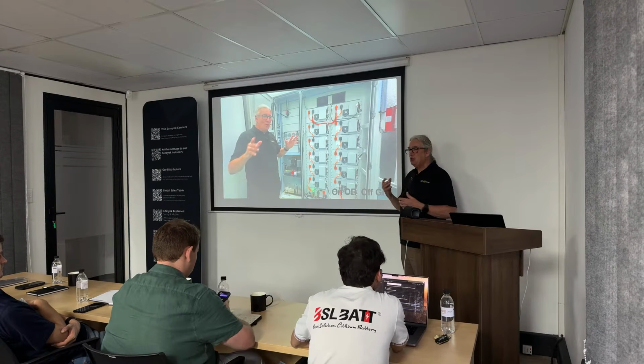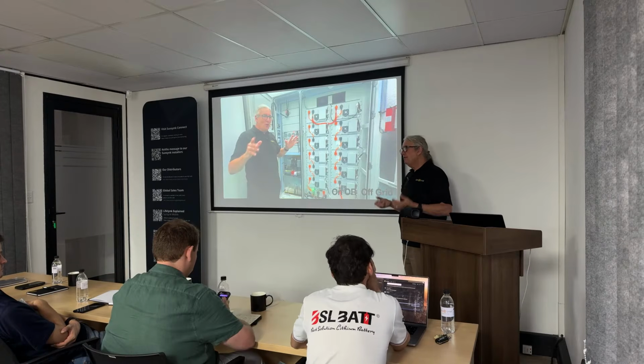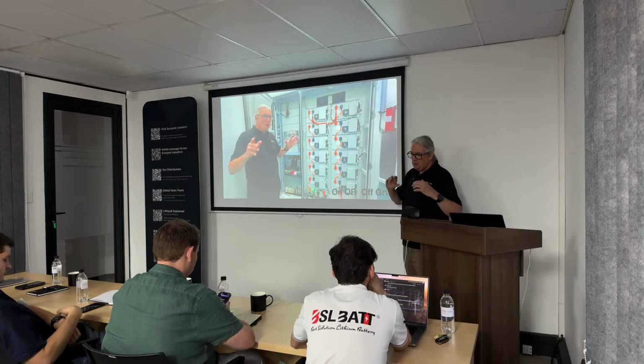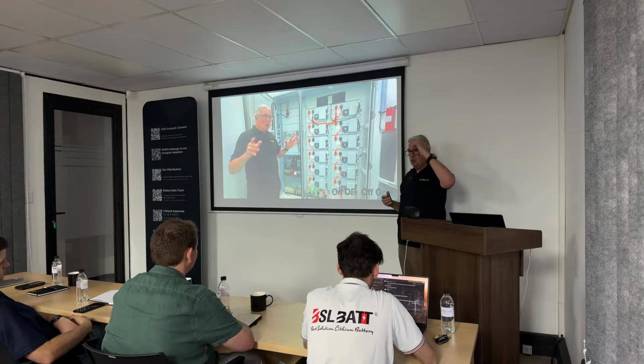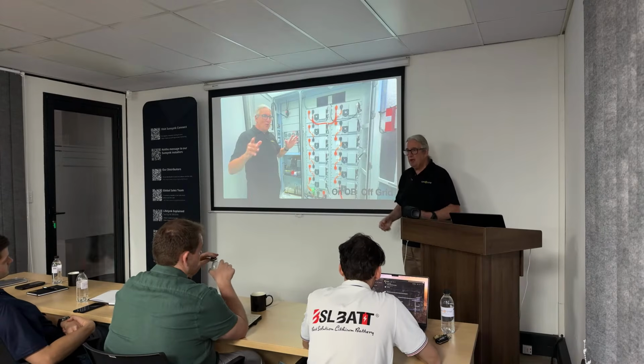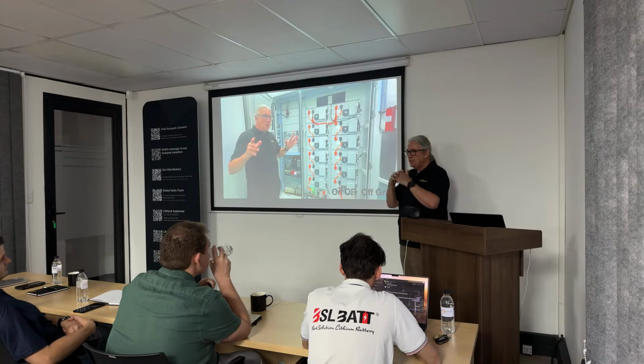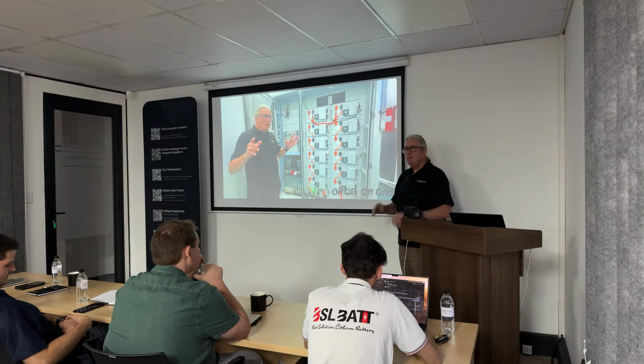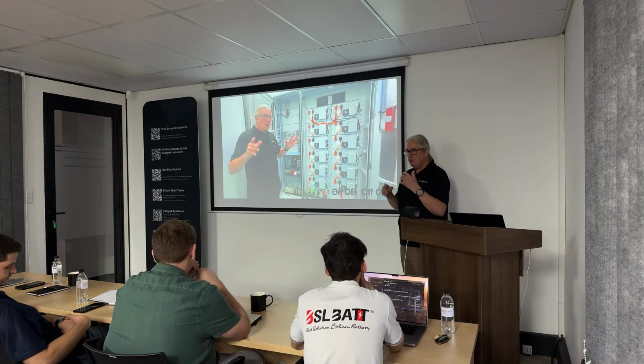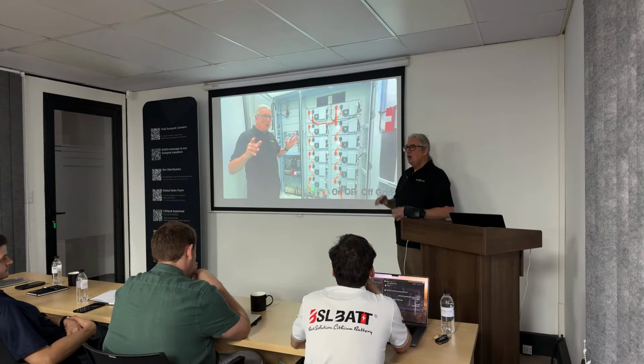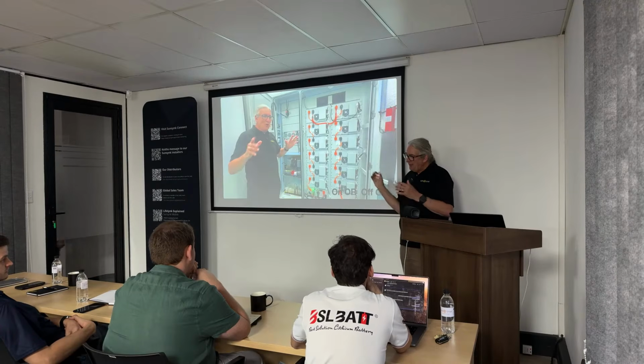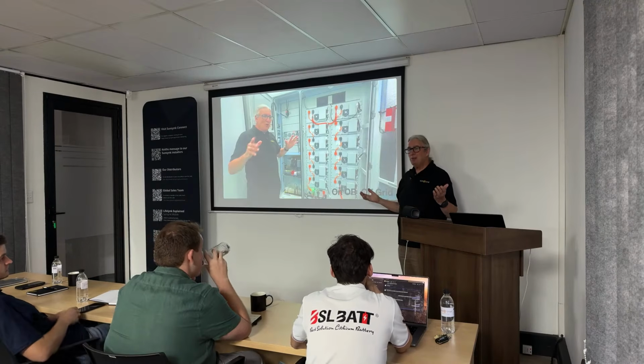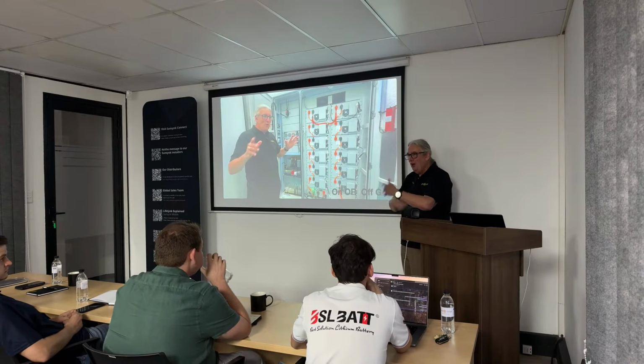There's no complicated changeovers, because so often with generators, when they change over, if they've got to supply the load - so if the generator's got to charge the batteries and provide the load at the same time - the generator comes into sync, the load hits, the generator slows down because the engine slows right down, goes out of sync, the frequency moves, thing drops out, and it's a problem. And it can go over and over and over again.